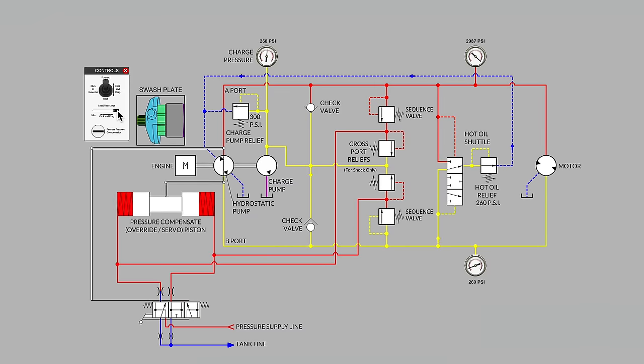Alright, something's very different from the last time. You don't see a continuous flow of fluid, you don't see those flow arrows continuously coming across from the overloaded side of the loop to the other. No, something very different has happened here. The sequence valve has popped open as the system is overloaded, sending a very small amount of fluid into the control piston. And the control piston built into the pump moves the swash plate to the neutral position, and the pump is essentially off stroke, meaning no longer displacing fluid.